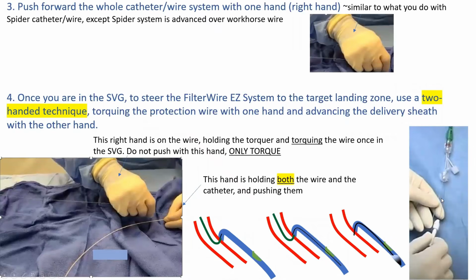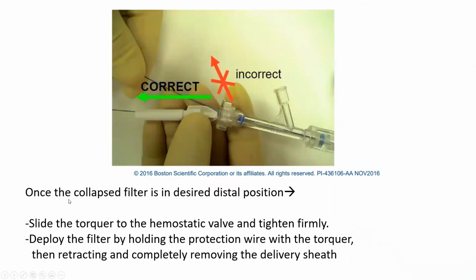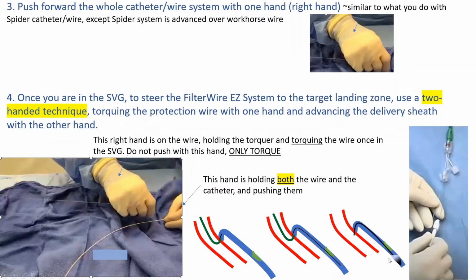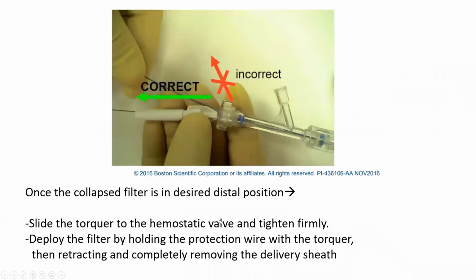Again, this is another illustration here. You torque with this hand, and you can use the torquer provided by the FilterWire EZ System. You torque with this hand while holding and pushing both with that hand, the left hand. Now, once the collapsed filter is in the desired position, then you're ready to deploy it similarly to the Spider basket. You pull the catheter while locking a torquer here and putting a slight push tension on the wire.